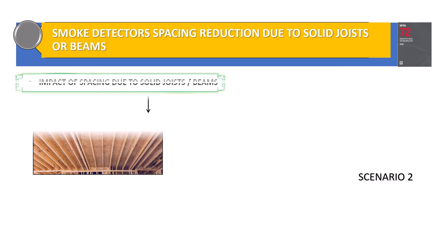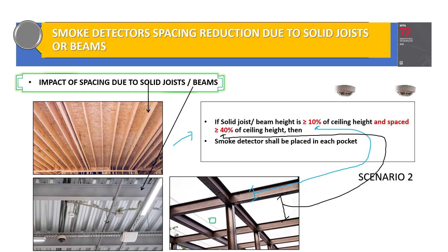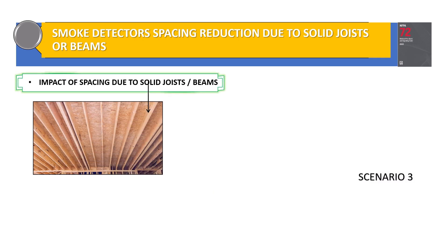In Scenario 2, you have solid joists or beams where the beam or solid joist height is greater than or equal to 10 percent of the ceiling height, and the spacing between the beams or solid joists is greater than or equal to 40 percent of the ceiling height. In this case, we need to place the smoke detector in each pocket, as you can see on your screen.